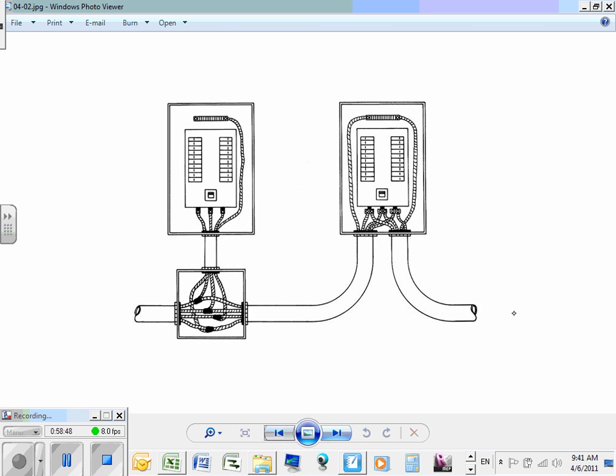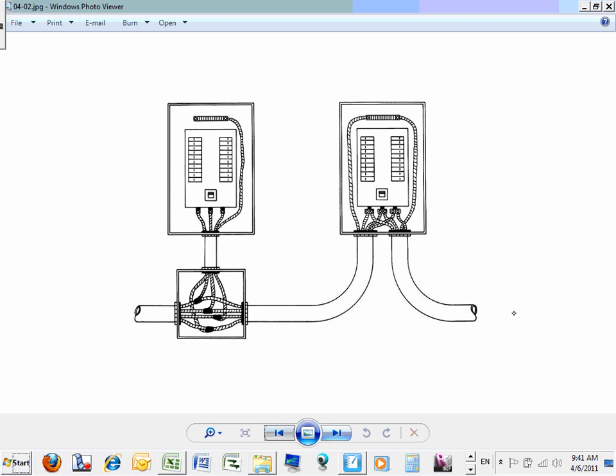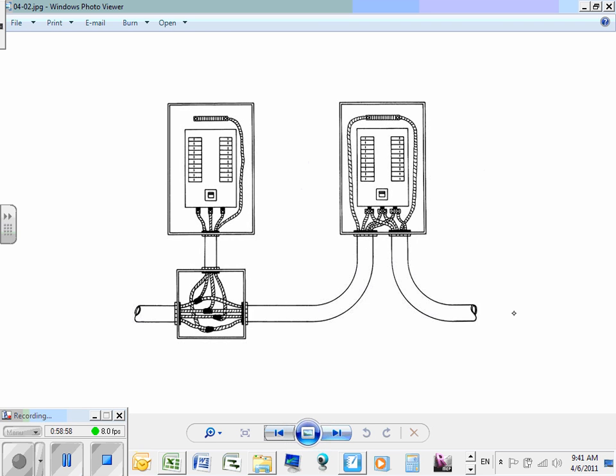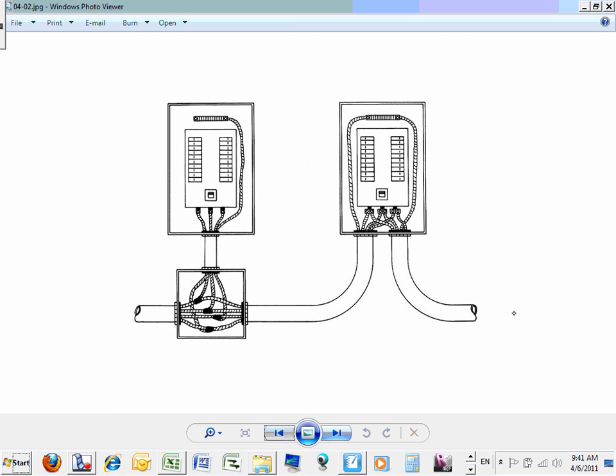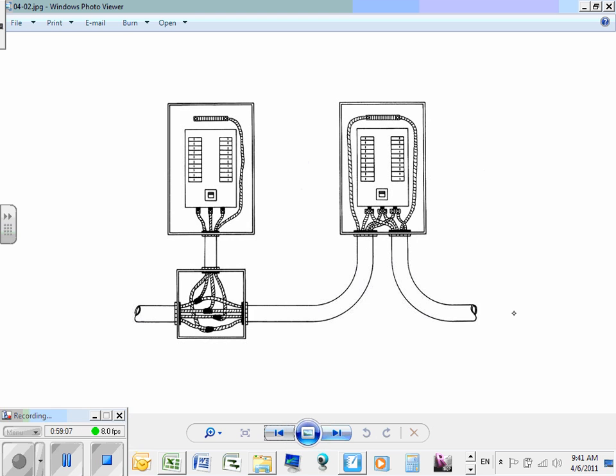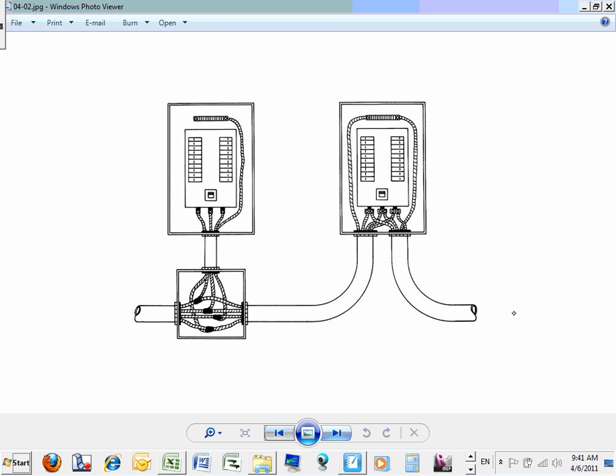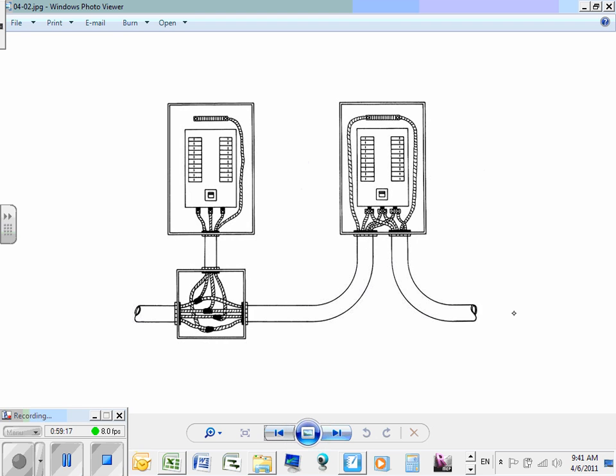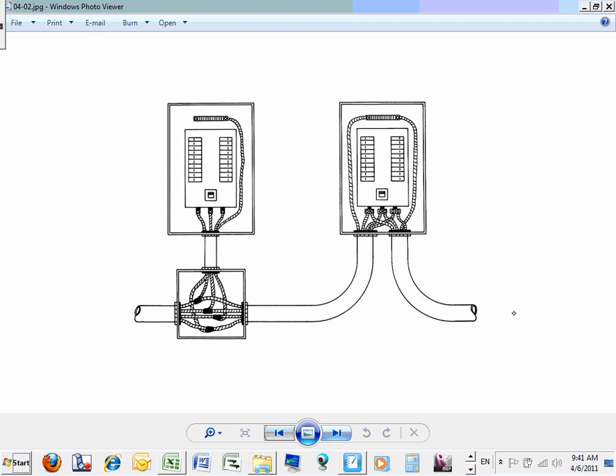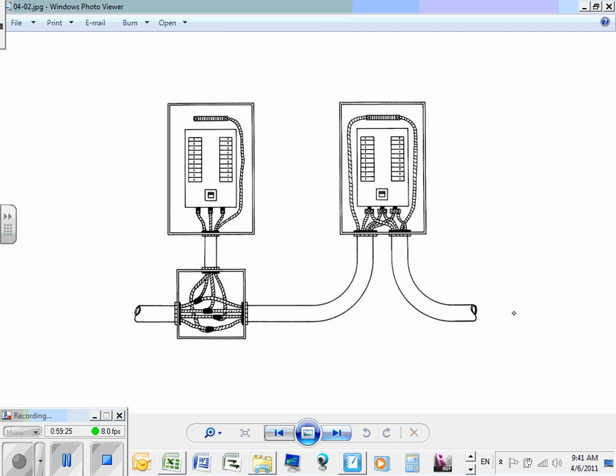Brad, this was a big deal when they limited us to 42 circuit breakers. It's no longer a big deal, because we can go as high as 84 circuit breakers. Feed through and sub-feed are not going to be a big deal. I can rack a 42 circuit breaker panel right now, or an 84 circuit breaker panel. And from a reliability point of view, guys, you don't want to put more than 84 circuits in one feeder. Are you kidding me? If you lose a feeder, you're going to trip 84 circuit breakers. That's as maximum as you can get.